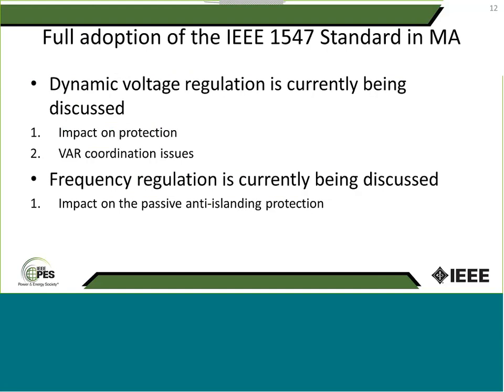Okay, so what's next? We just talked about ride-through only. Of course, 1547 is the big standard, which covers voltage regulation, frequency regulation, islanding, secondary network interconnections, and there's a big list, with interoperability being another aspect. What's the plan for the future, or the near future, I should say, when it comes to adopting the standard in Massachusetts?